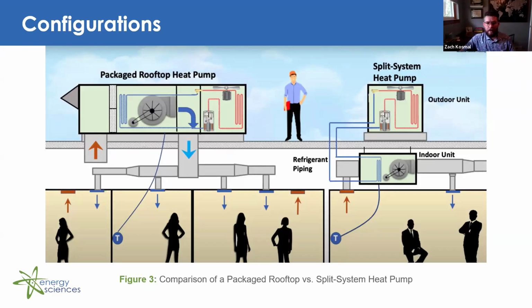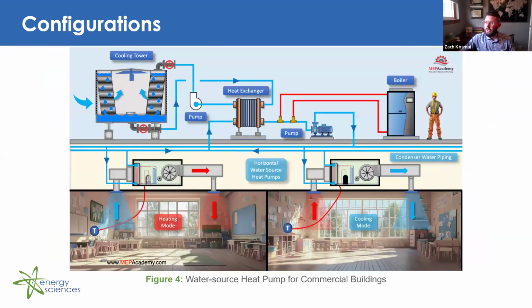With regard to hot water heating systems, this would be an applicable system for that, where your water source heat pumps may operate with supplemental heating from that boiler when needed. So it's more of a backup with regard to hot water heating systems.